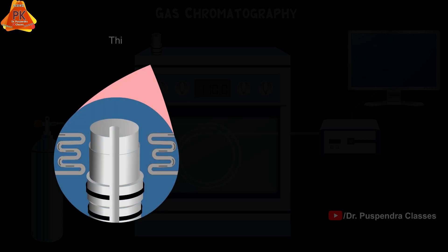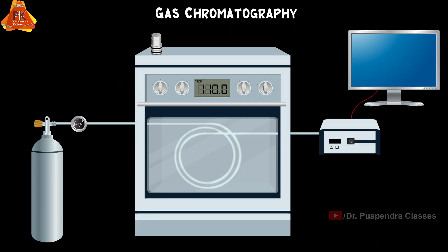But if we are injecting liquid sample, then it will be converted into gaseous form due to heating created by heated metal block present in the sample inlet part. The vaporized liquid sample will move towards the capillary column.